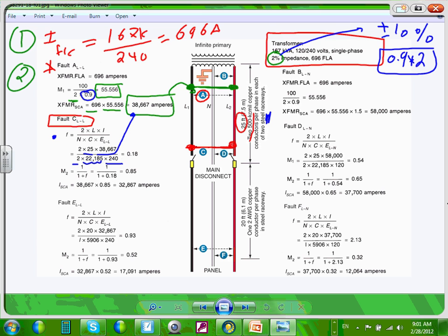Okay, everybody knows how the 22185 came to be. How about the 240, the voltage? When you do that, you end up with an F factor of 0.18. Then you use this formula to convert it into the M2 factor. They call it the M2 factor. 1 over 1 plus F, just plugging it in, equals 0.85. Then you multiply this number here, can you guys see that, by the new factor, 0.85. Now I end up, right at this point, with 32,867 short circuit. Can I get you guys to understand that the highest short circuit is going to be at the terminal of the transformer? The further away I go from the transformer, the less the short circuit would be, right? Can you guys see that it was 38.6? When I went 25 feet down, it dropped to 32.